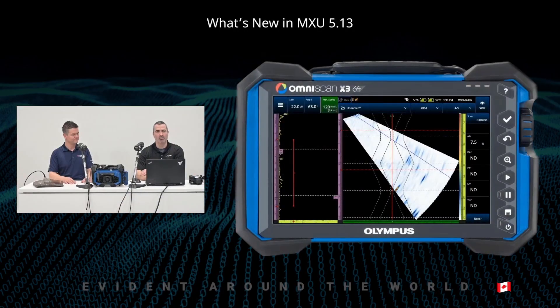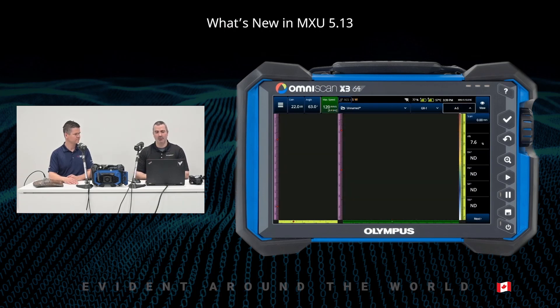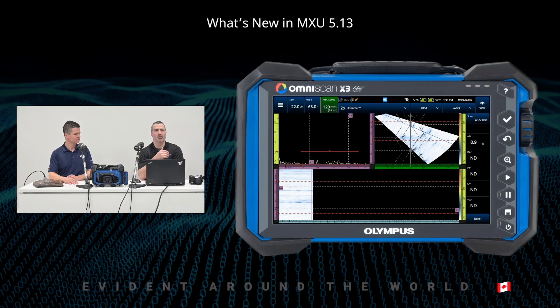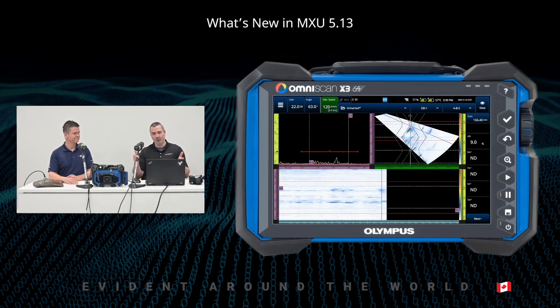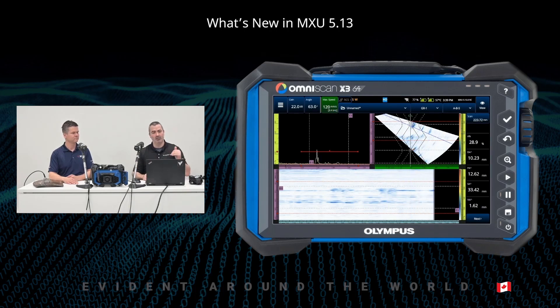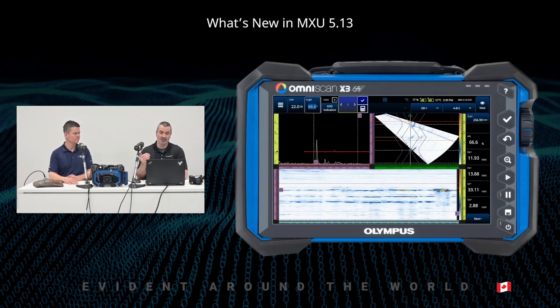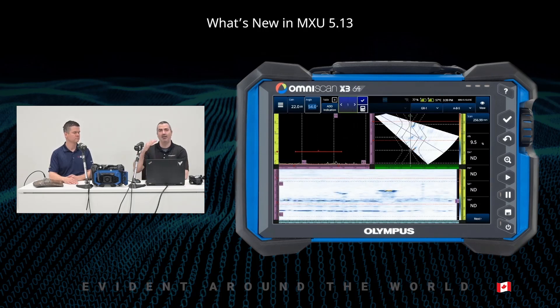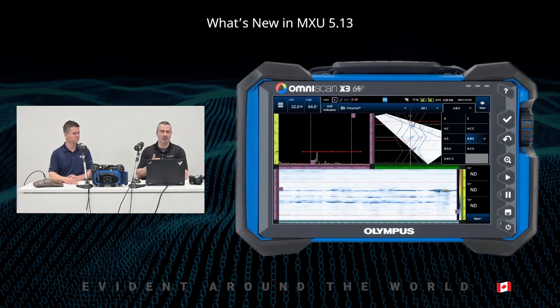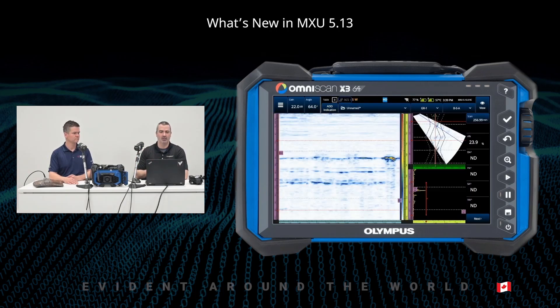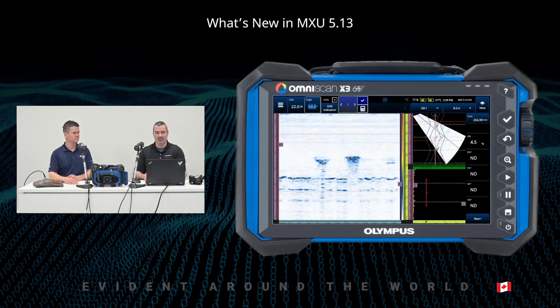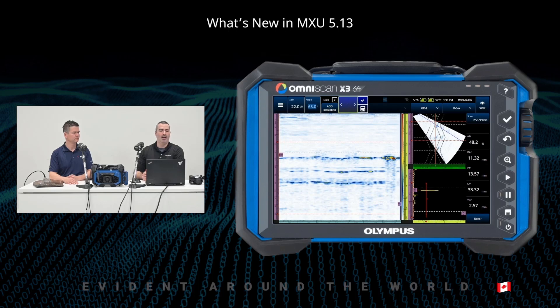To illustrate that, we have data acquired on an OmniScan. We have our A-scan and our S-scan, like we see traditionally coming out of the wizard. If we turn it to an ABS layout, we have the scanner movement. As mentioned, we have only the display of one angle or one focal. So although we see multiple defects or indications in the A-scan and S-scan, we only see one at a time and still have to scroll from max angle to min angle. We have a new B-S-A layout that takes better advantage of the screen, but it's still the same deal.